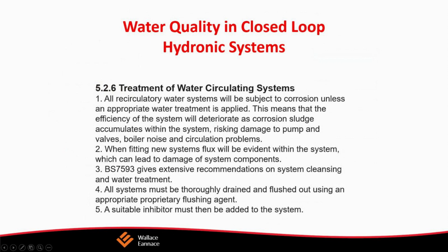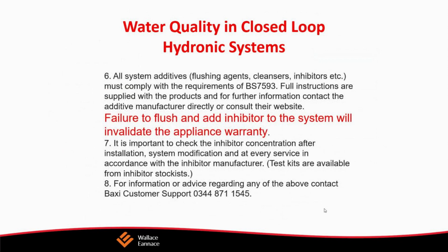When this system was designed, the pump was selected to operate at a certain flow rate, giving feet of head. Well, you can be sure that when you get all this corrosion around the outside of the pipe or the inside of the pipe, the corrosion is going to dramatically change the flow characteristics and the head characteristics. Now, that pump, which was originally specified for this system, is no longer going to behave properly. And then it causes all kinds of problems. Not only do you lose efficiency, but you can also get failures.